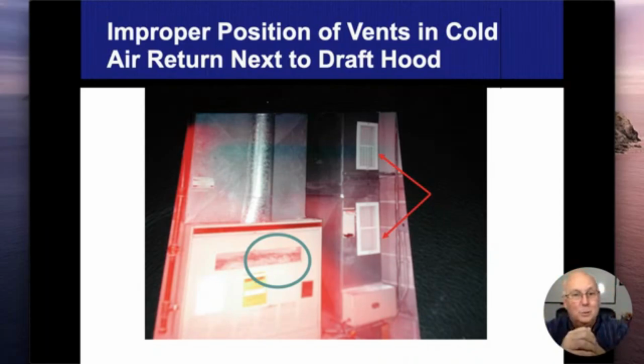So the solution to that, and not a very good one, but it is a solution, is somebody can cut in those openings that we're seeing on the return duct where those two red arrows are pointing. And that way we're not going to depressurize the rest of the ductwork. But then again, we're also not pulling air out of those rooms either. All right, so that's going to make the air circulation from the rooms less efficient as well. I know the real solution is expensive, which means putting in bigger ductwork or additional ductwork, and that's not something that people normally want to spend. So they try to go ahead and find a solution.